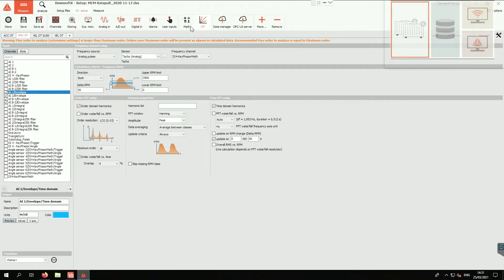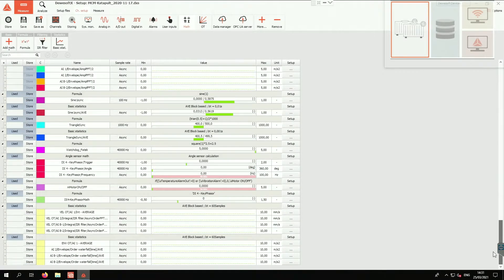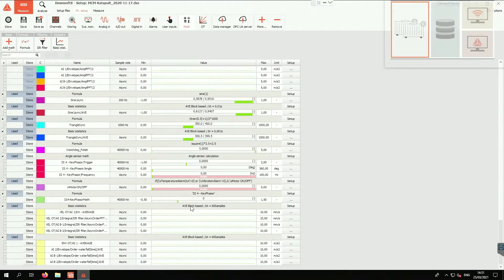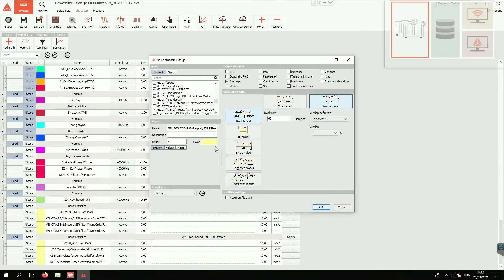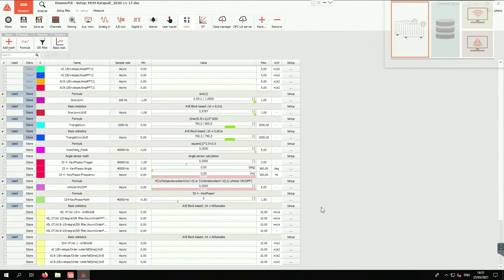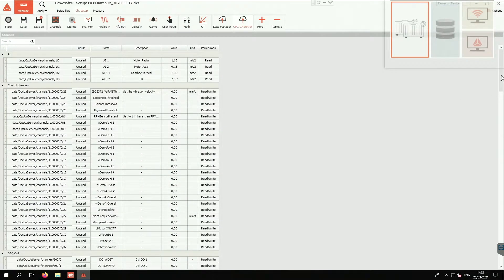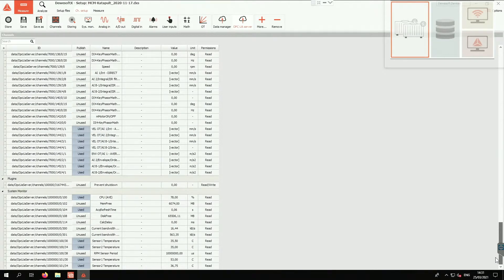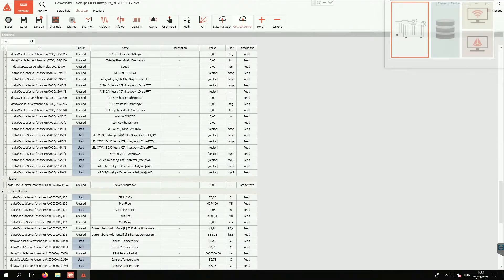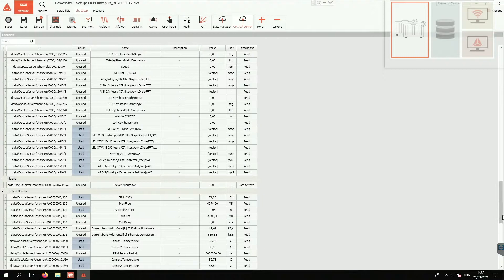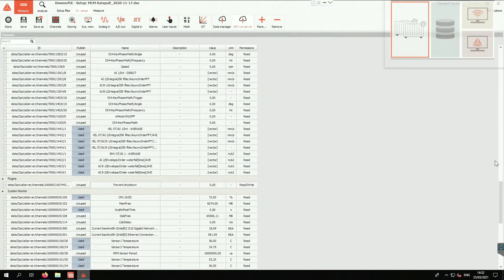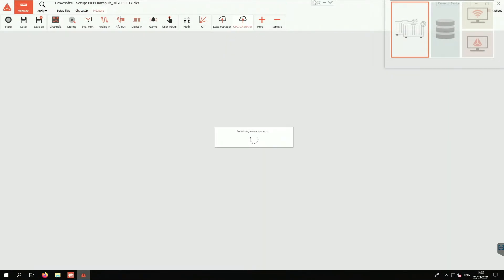Then we are also again averaging this order tracking that comes out. So right here we have another average so that we are averaging order tracking over one minute. Each one minute, another order tracking FFT comes out of the system. This is how it's set up: the order tracking as an input and then averaging 60 seconds. This means that we now finally enable this order tracking average in the OPC UA server. It's this one here, basically those channels. Of course, we're also monitoring the normal vibration velocity, but let's focus now on the envelope signals. We go back to measure mode here and we go to our web clients that we haven't yet touched.